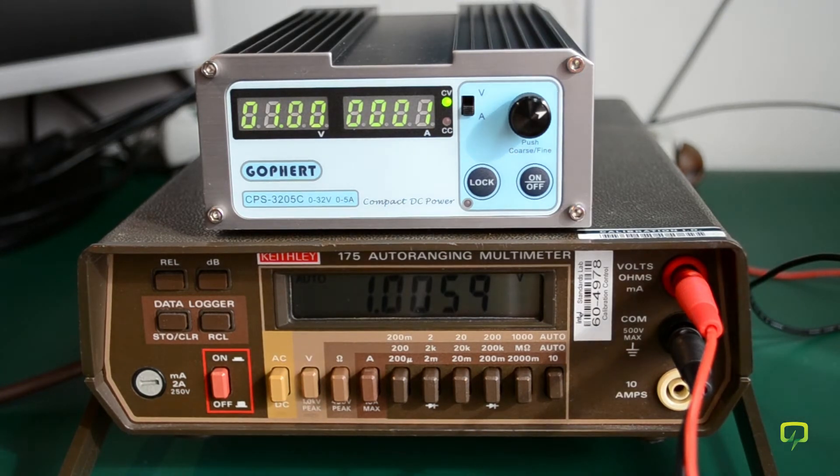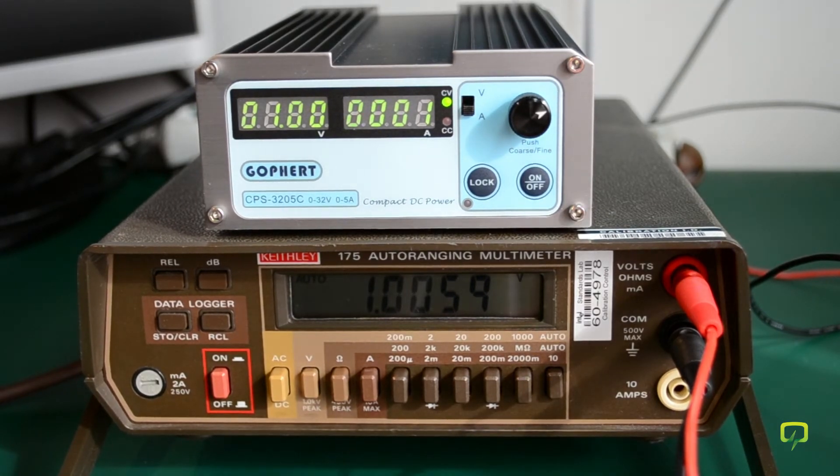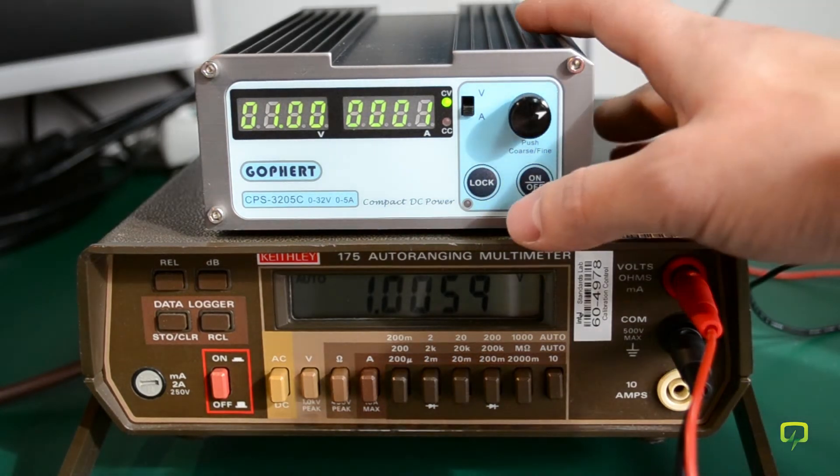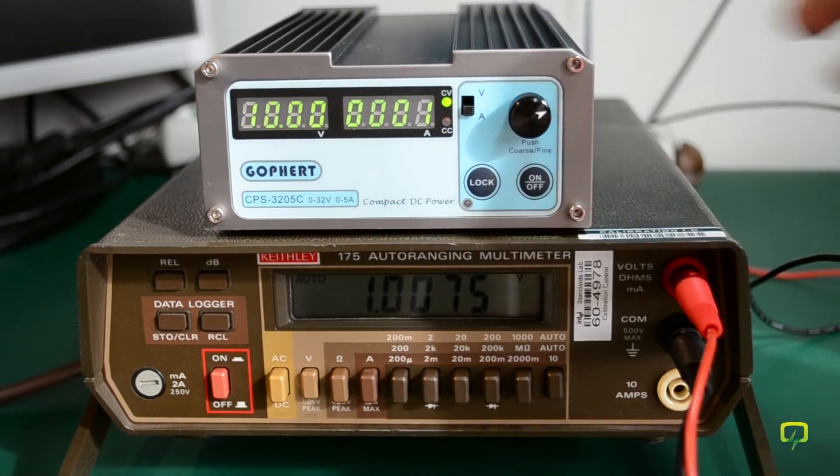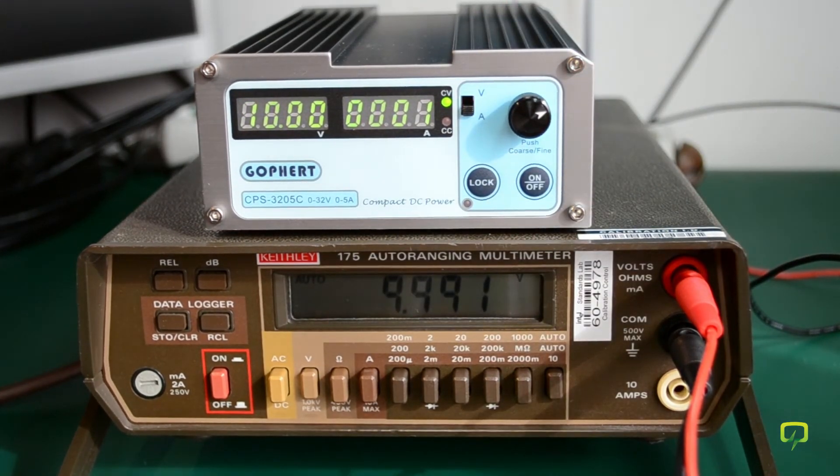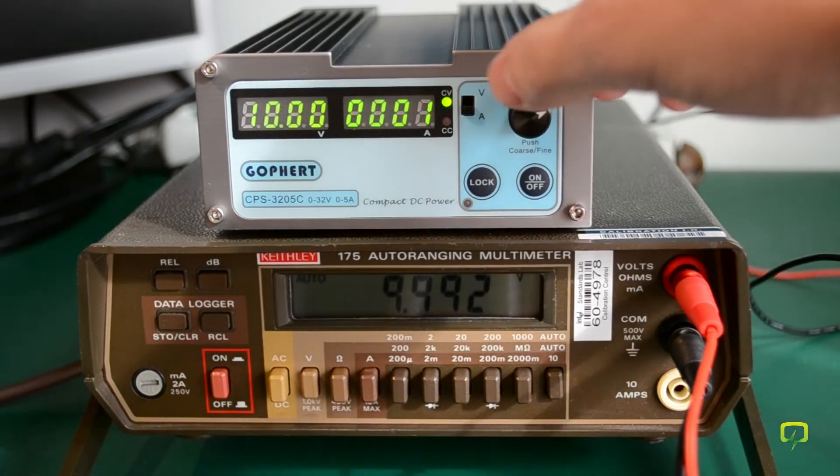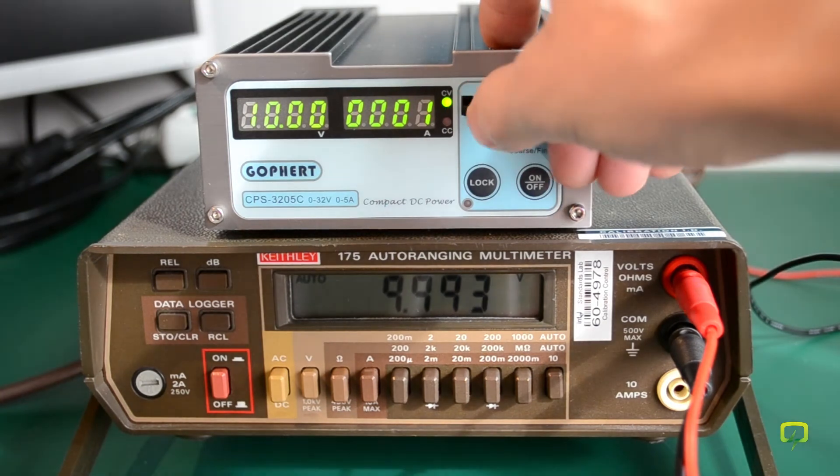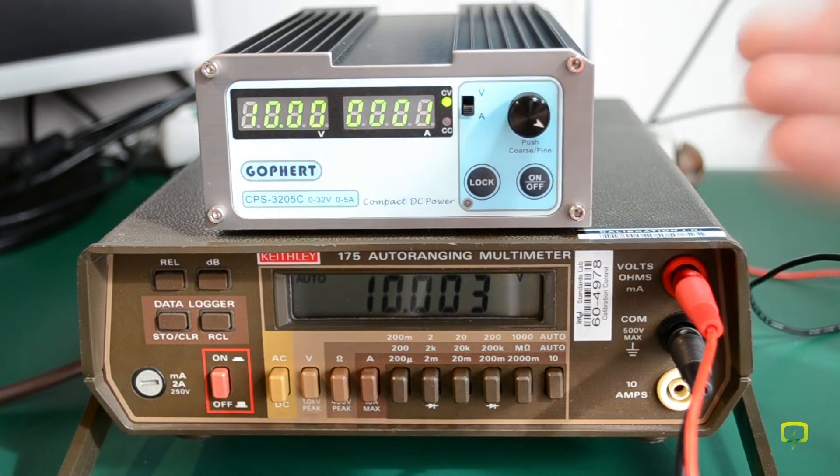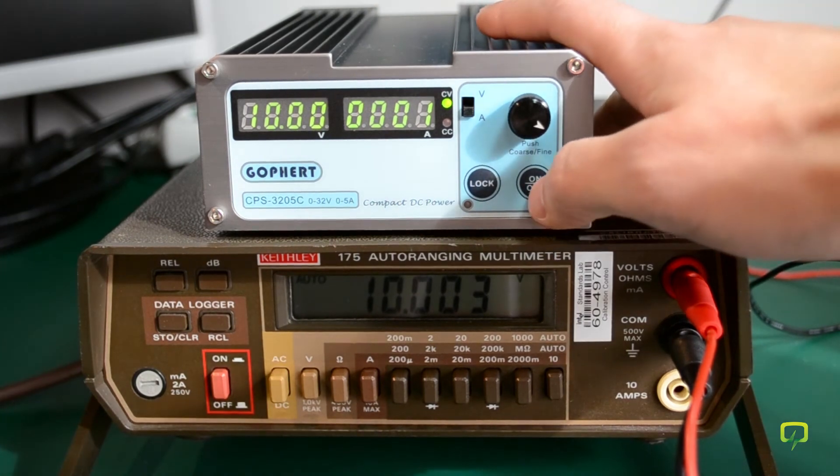Next, if you're happy with the measurement, you press the on/off button to calibrate the output voltage for different ranges. So I press the on/off button once, and it went to the 10 volt mark. Now you have to calibrate it for 10.00 volts. So let me try to adjust that. Okay, I have 10.00 volts. Now you press the on/off button again.